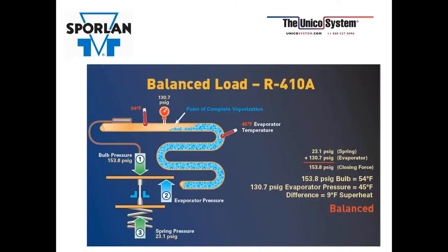So as the load, look at a balanced ported valve, a balanced load here. If you notice, the bulb is sensing 54 degrees. If you use your PT chart, that determines that the opening pressure that the bulb is formulating is 153.8 psig. You have 130.7 pounds for the equalizer pressure, and then you have 23.1 pounds for the spring pressure. So you add those two closing factors together, it's 153.8. So you have 153.8 in the opening force and 153.8 in the closing. So it's a balanced position.